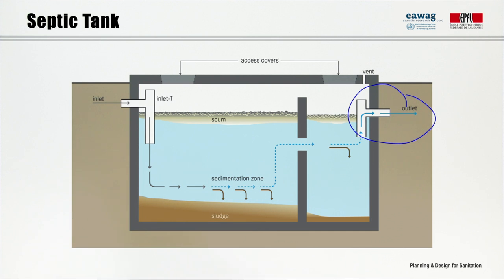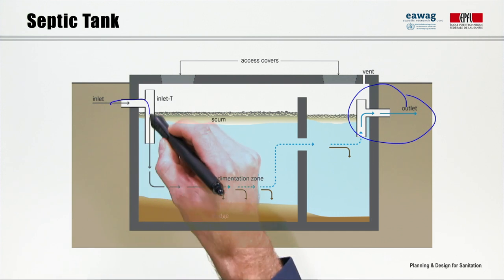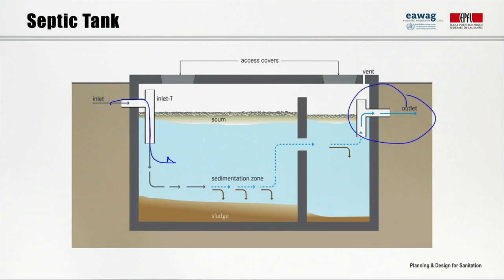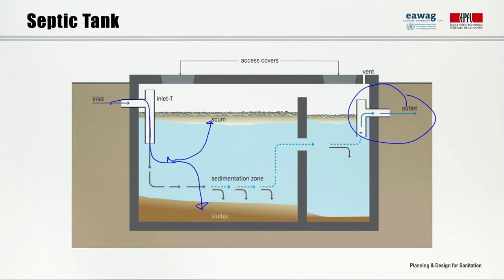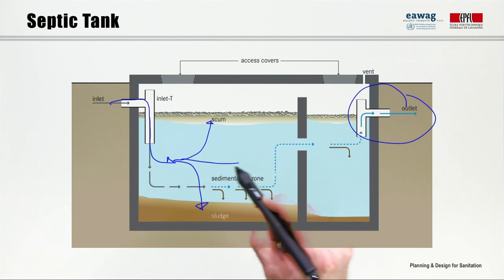Blackwater and greywater enter the tank through an inlet T. Settlable solids fall down to the bottom, where they accumulate as sludge. With time, the sludge undergoes some stabilization by anaerobic digestion, and it has to be removed every three to five years. Floatable substances move up to the surface, forming a scum layer. The effluent from the clear water zone in the middle flows out through an outlet T and is then typically infiltrated, for example in a leach field.